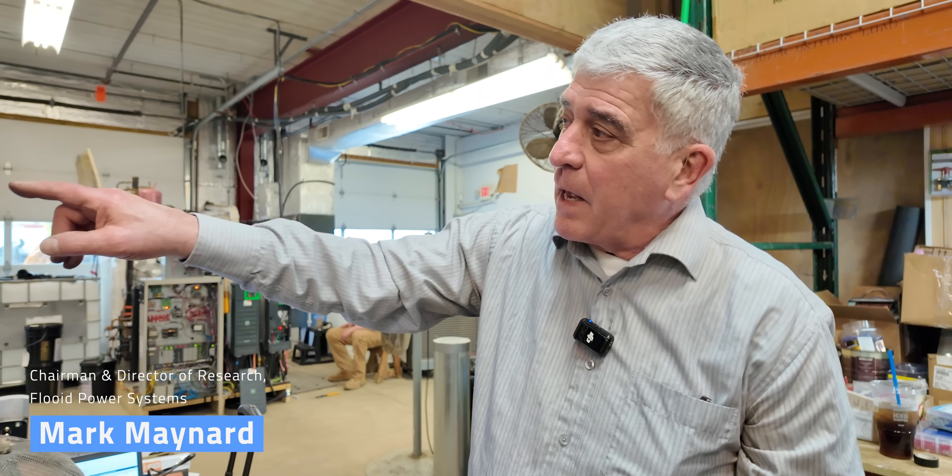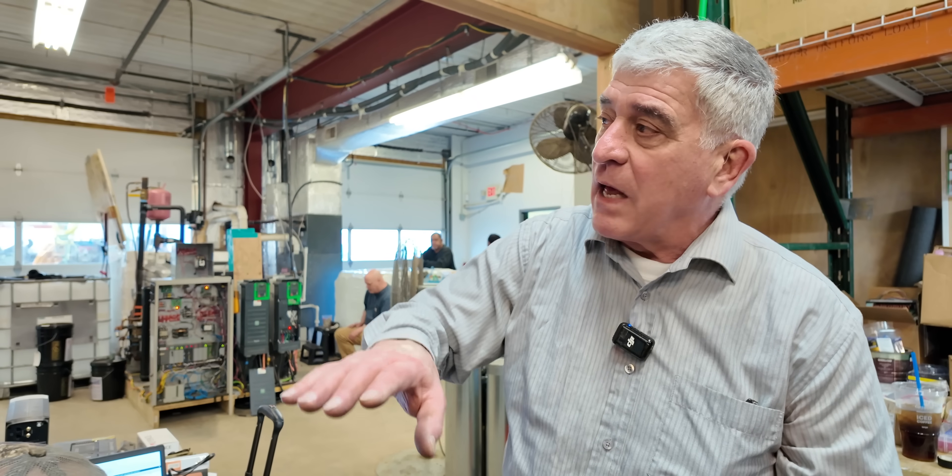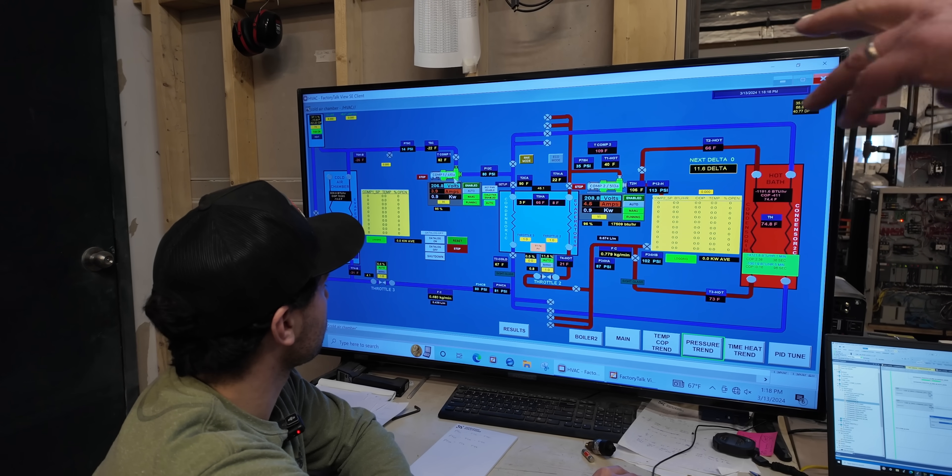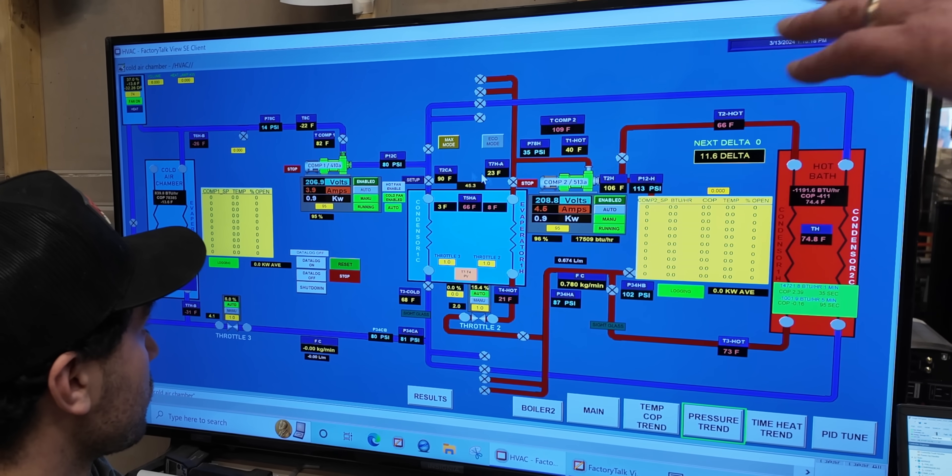It's not a perfect analogy at all, but it's kind of like having multiple gears on your bike versus just one. This is Mark Maynard, Chair and Director of Research for Flooid. He showed me around Flooid's lab in East Hampton, Massachusetts. "This is going to start pumping out some values very soon. And when it does, you'll see that minus 11, which is lower than almost anybody can do right now, but you'll see that our capacities are still high and our COPs will be very high also."